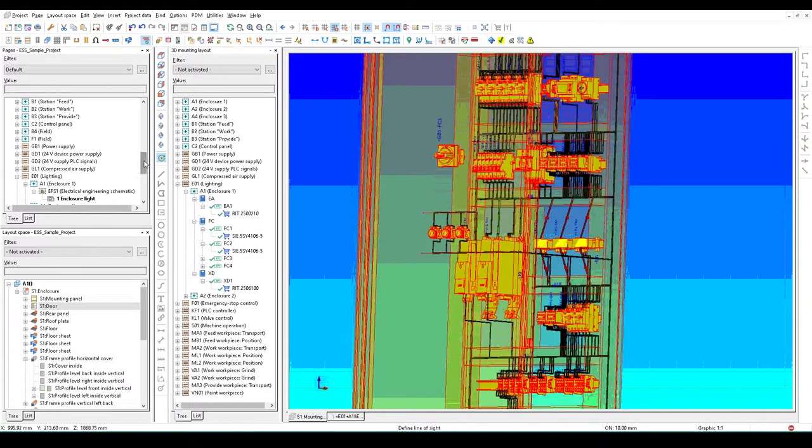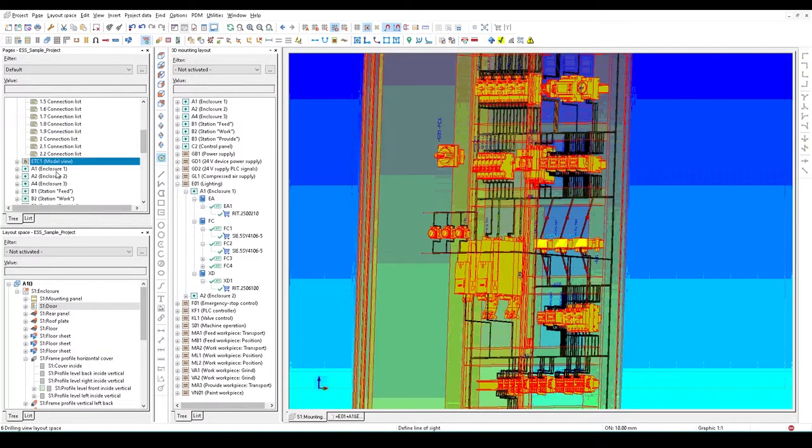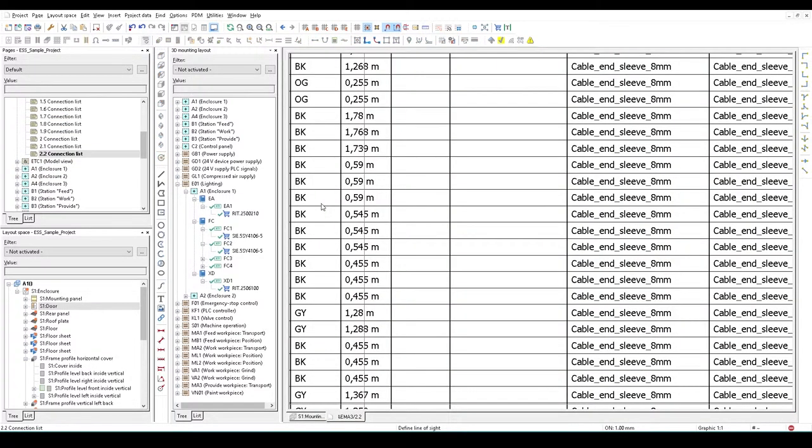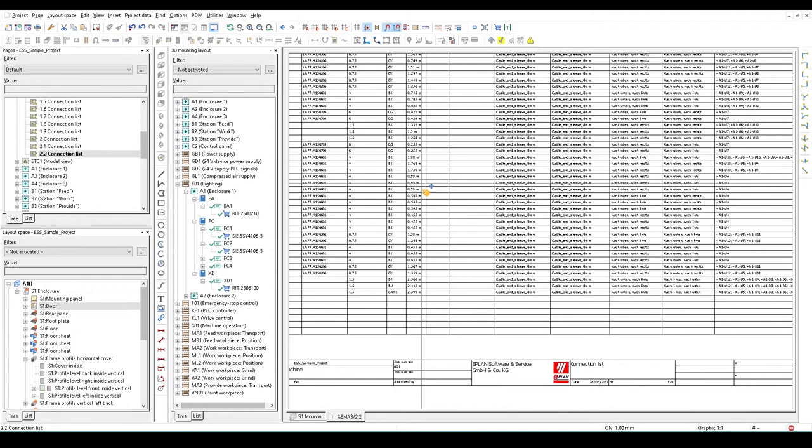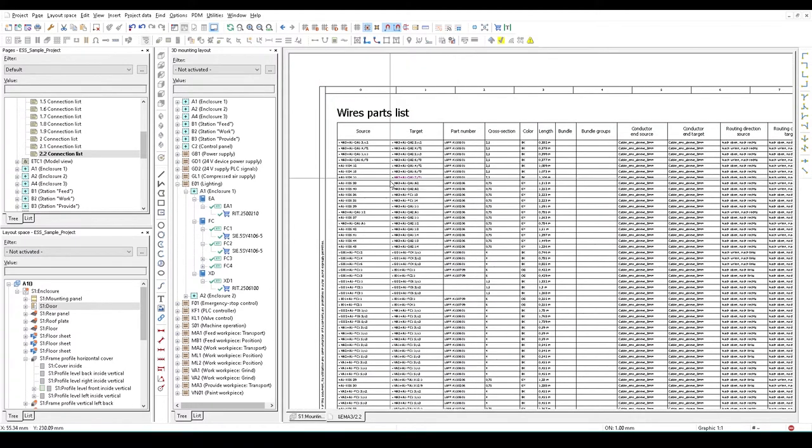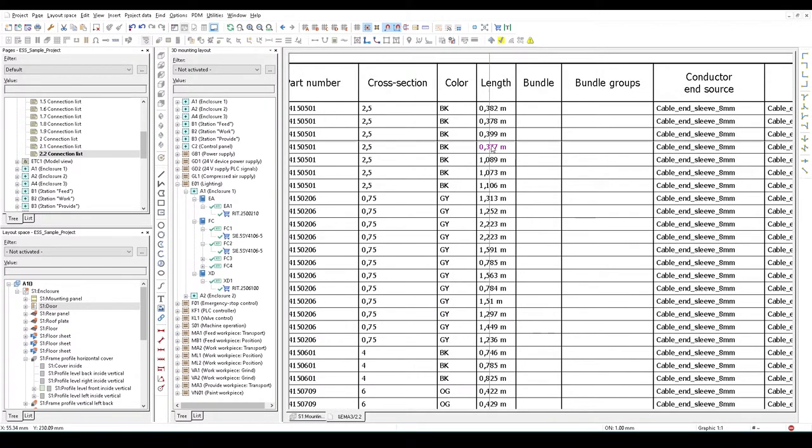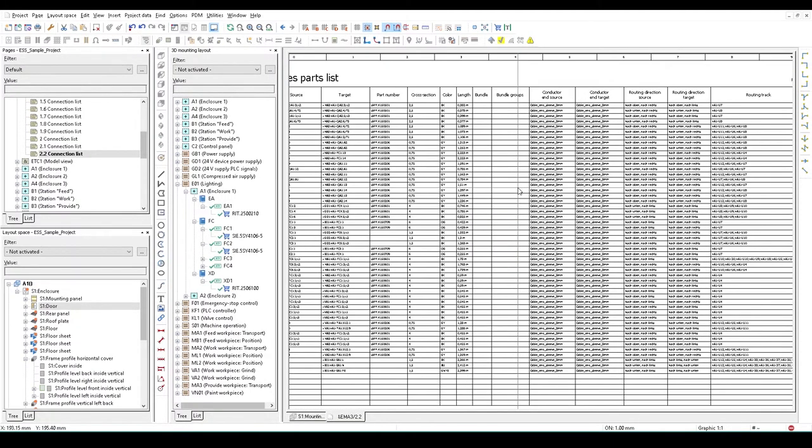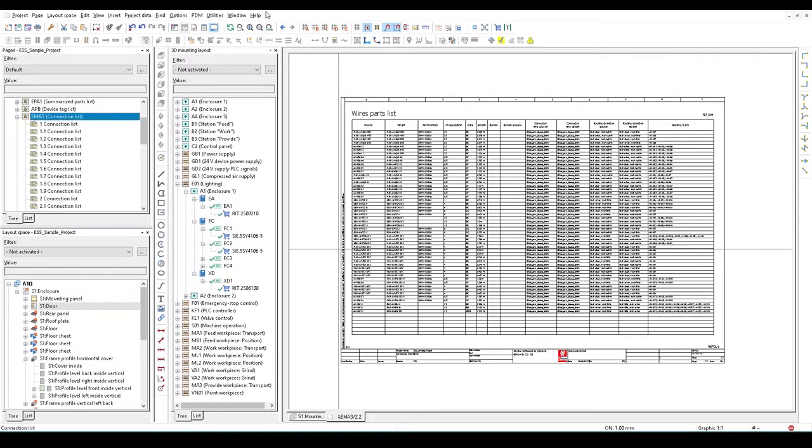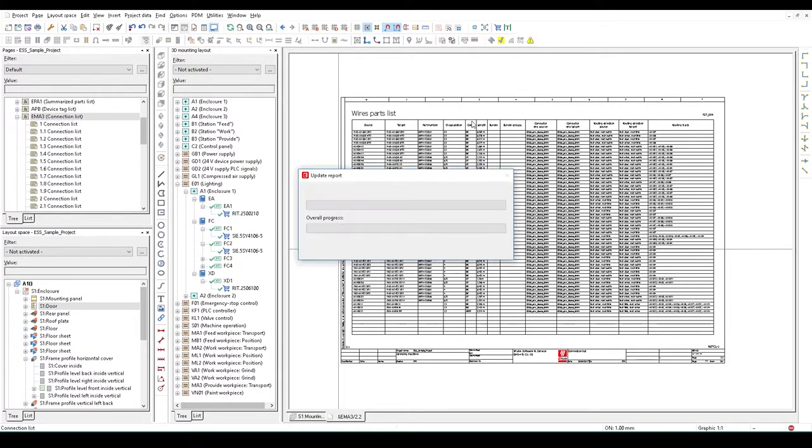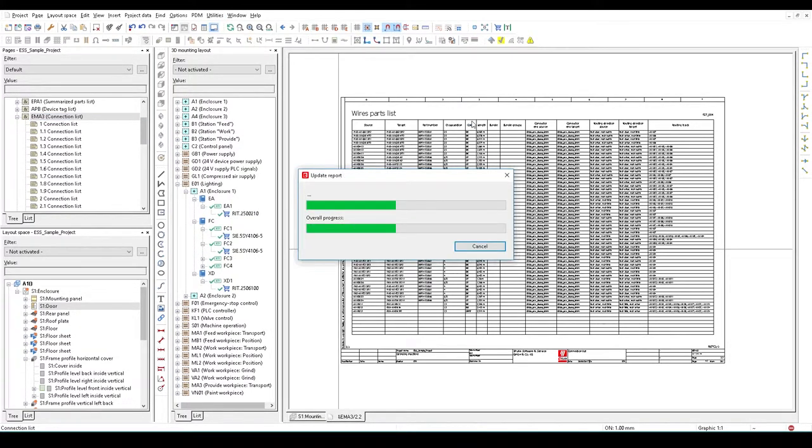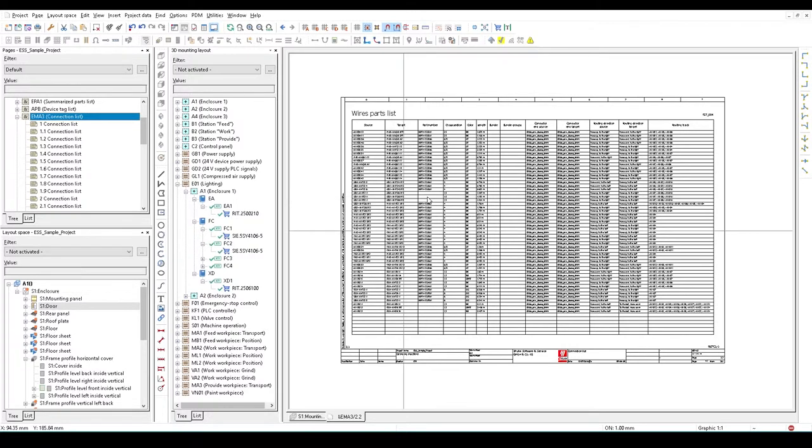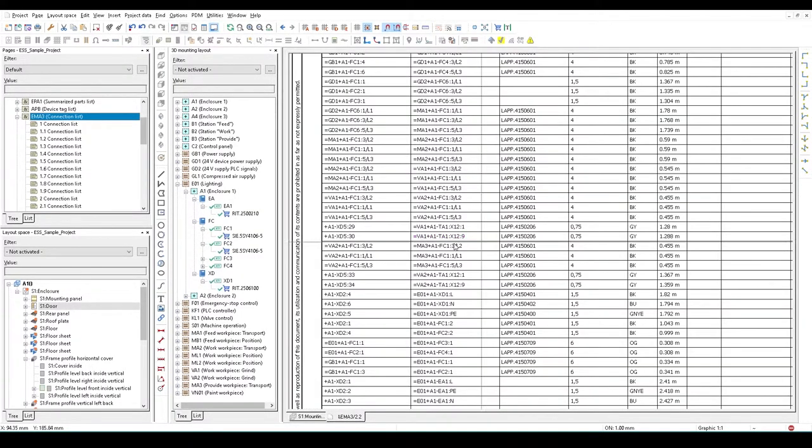The nice thing about a connection list is it can be reported. Here's the connection list. I can see the size of the wires they need to be, part numbers against the wires - source, target, part number, cross section, and color. Data can be passed through very easily and it's an updatable report. I've made some changes to this one. Very quickly, I'll go to the report and update. That's going to update my reports from the latest wiring set.